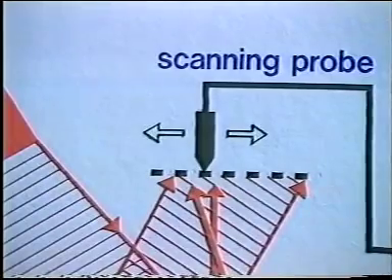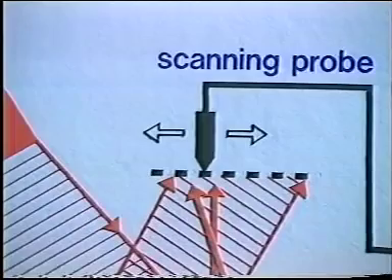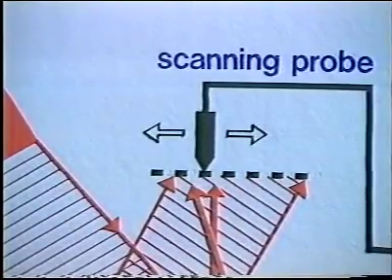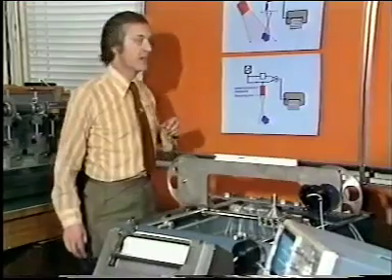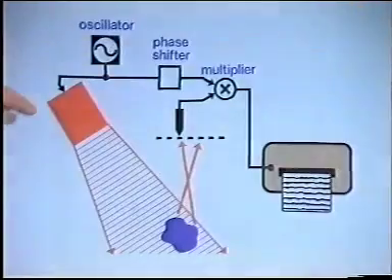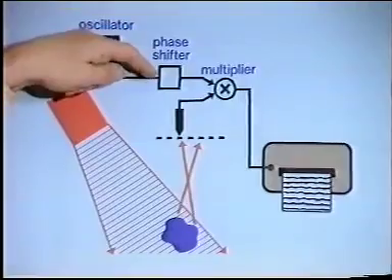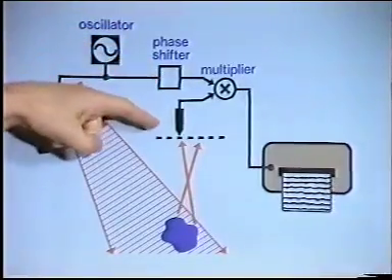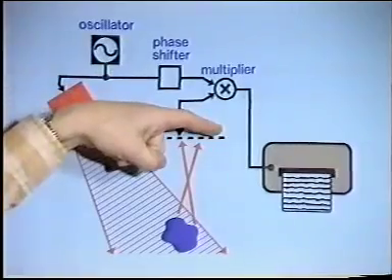So if we're going to reconstruct, or rather simulate, a reference beam electrically, we've got to have an electrical signal which progressively changes phase. So if we go back to that third diagram again, what it means is that we have this phase shifter whose phase must increase progressively in synchronism with the mechanical movement of the transducer across there. And that's what's done.